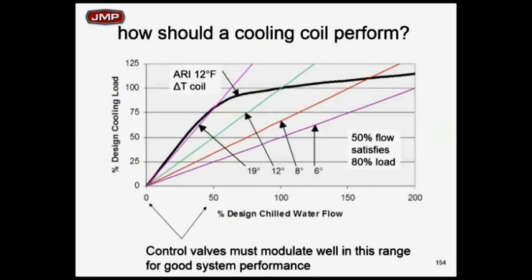Let's look at half flow in GPM through a typical ARI certified cooling coil. See what we would predict would happen to the ability to cool. Let's see what we would predict would happen to the delta T. So if you went to 50% design flow and you go straight up, where are you coming out? Looks to me like we're running in the neighborhood of 75 to 80% cooling. Take the 50% straight vertical line up to the black line. The black line is the coil line. To the left, I'm seeing about 80% cooling. Wow. At half flow, in theory, I'm going to get 80% cooling.